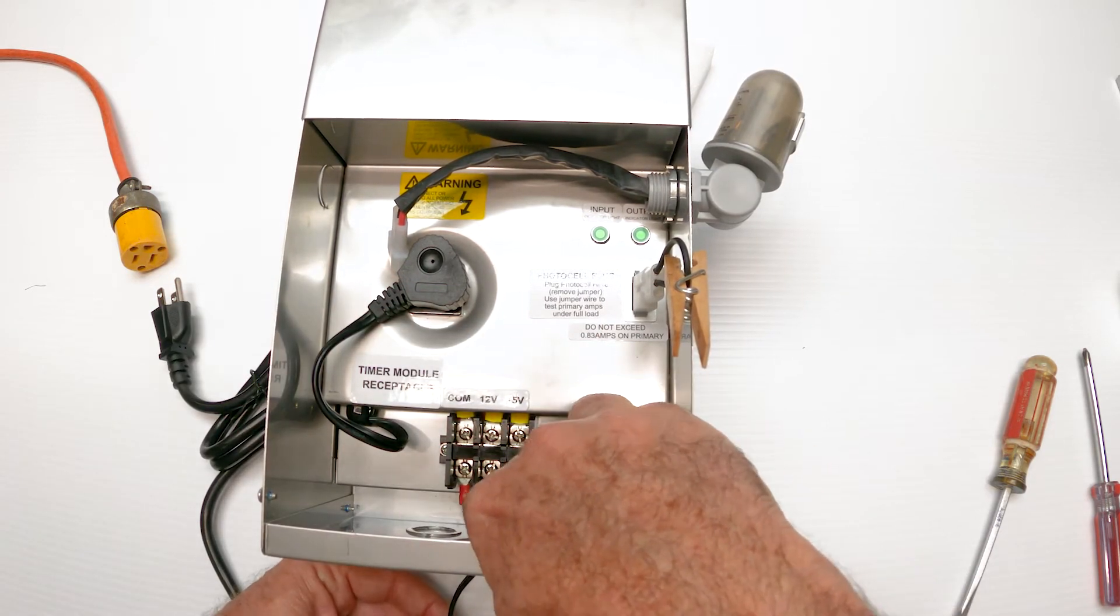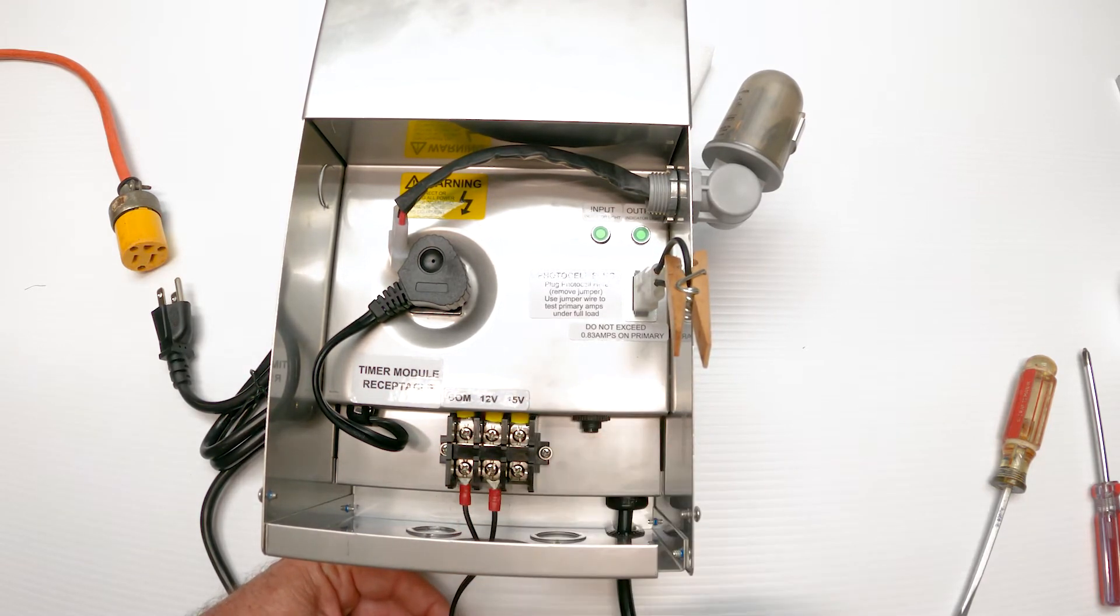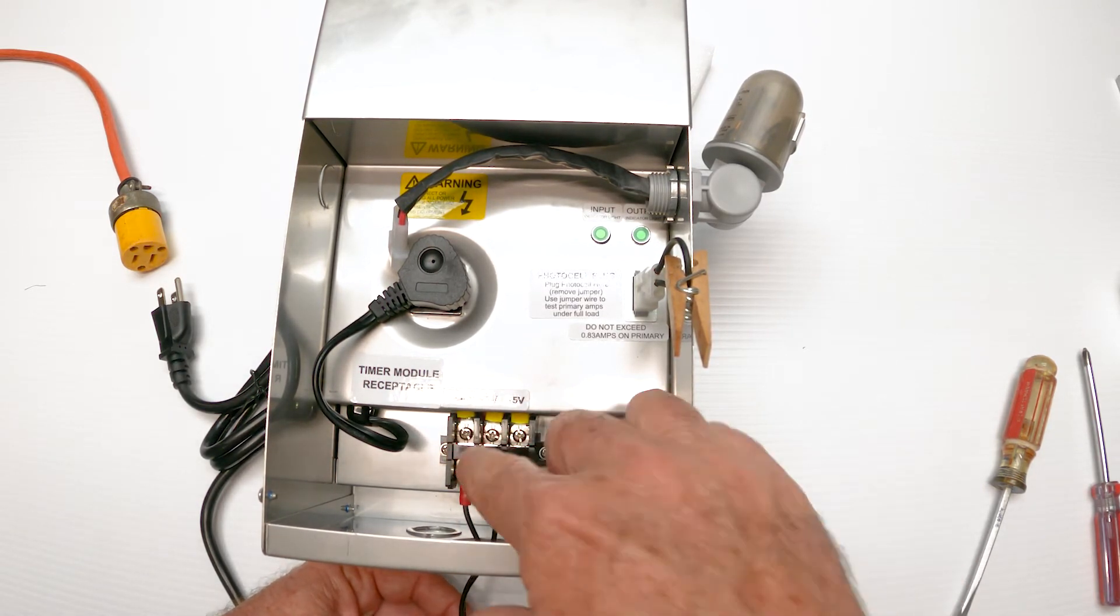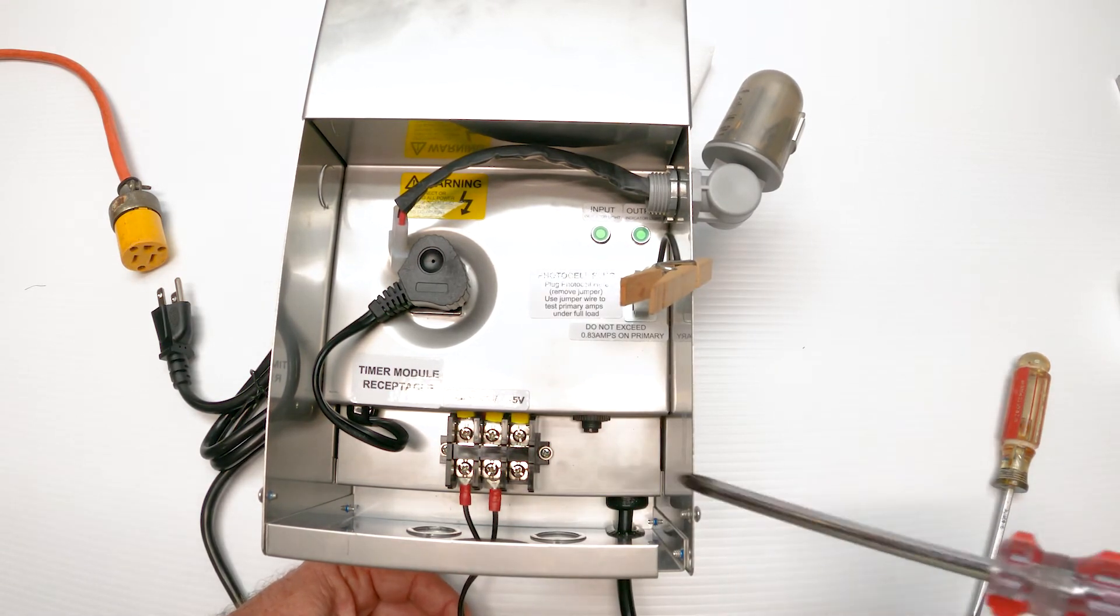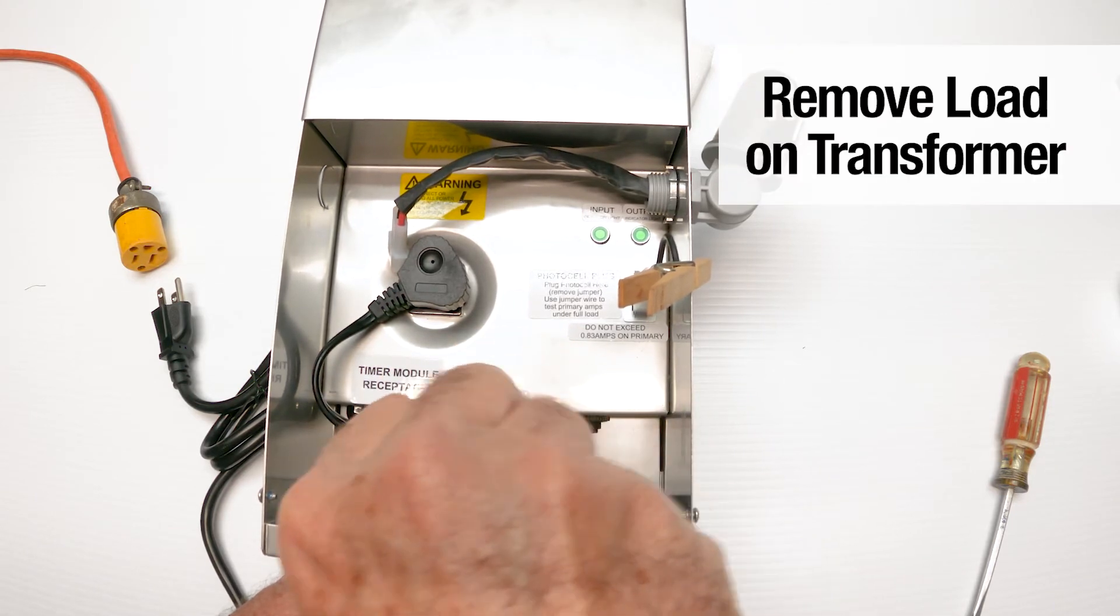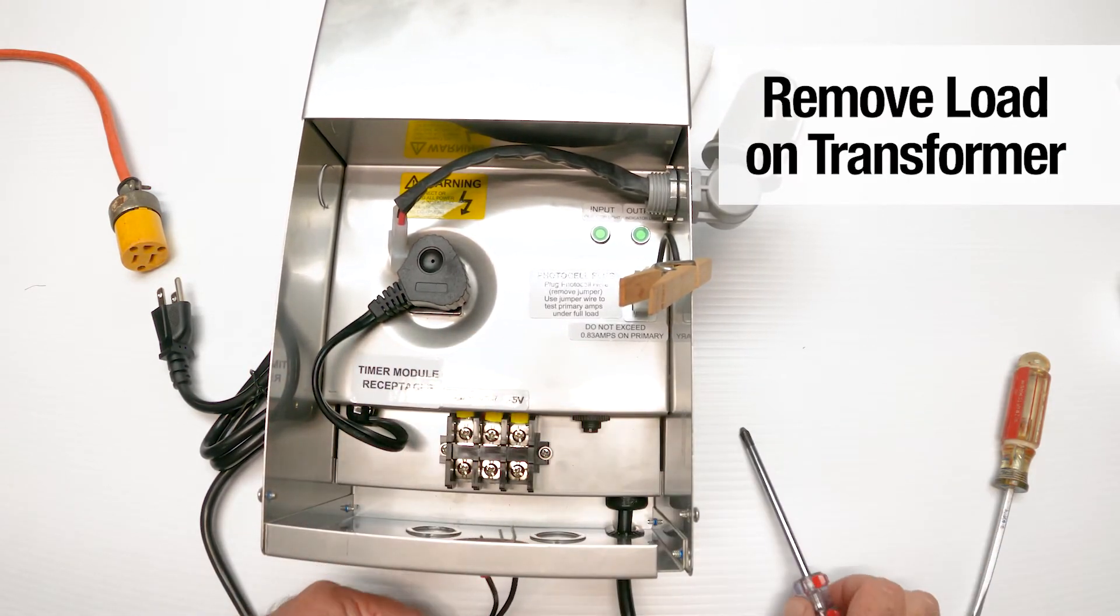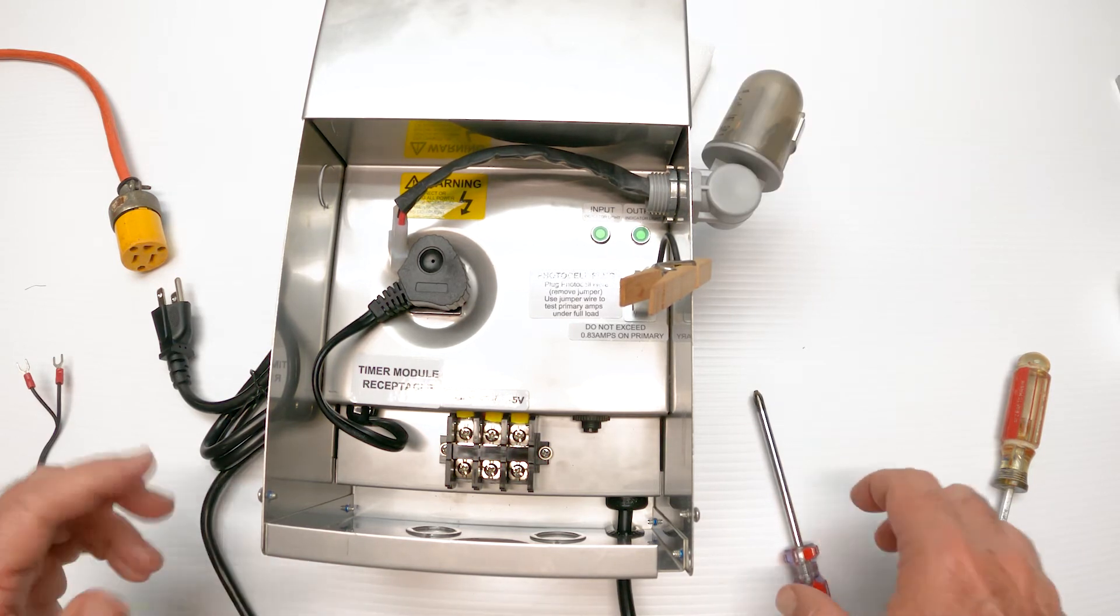The power going from the unit, 12 volts out through the wire is still connected. This may be the problem. There may be a short somewhere outside on the run. So I am going to come in here with my screwdriver and I'm going to remove the load.